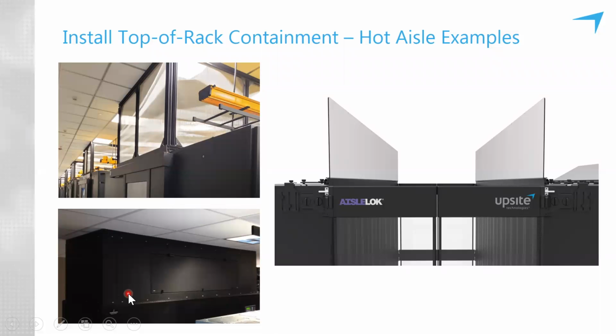What you see in the top right is a rigid hot aisle containment design. It's using rigid panels to make that perimeter from the top of the rack to the ceiling. There's also a play here for flexible hot aisle containment, using curtains, the flexible polycarbonate wall material that can be used. People usually associate curtains with meat lockers, but there's definitely a play for them in hot aisle containment, specifically when you have varying elevations of power and cable management. So you see ladder rack and then a yellow fiber tray here. They're running parallel to these rows, but oftentimes you have things cutting across the rows. So it's tricky, right? You've got to navigate around different widths, different heights, different elevations.